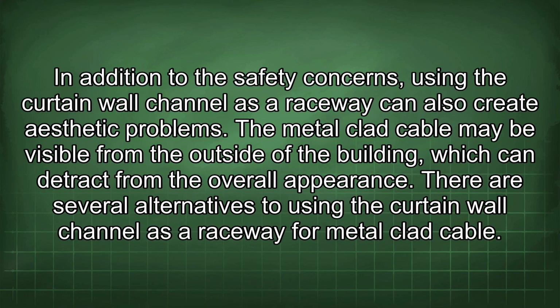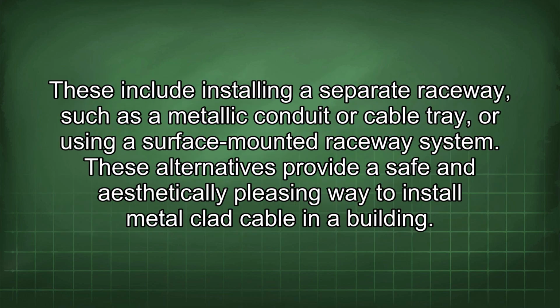In addition to the safety concerns, using the curtain wall channel as a raceway can also create aesthetic problems. The metal-clad cable may be visible from the outside of the building, which can detract from the overall appearance. There are several alternatives to using the curtain wall channel as a raceway for metal-clad cable. These include installing a separate raceway, such as a metallic conduit or cable tray, or using a surface-mounted raceway system. These alternatives provide a safe and aesthetically pleasing way to install metal-clad cable in a building.